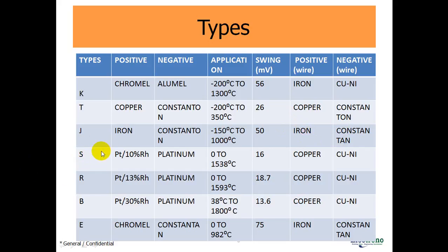Type S: it is made by platinum and 10% rhodium — meaning 90% of the material used is platinum and 10% is rhodium. The negative lead is made by platinum. Application is 0°C to 1538°C, voltage swing is 16 millivolts, and the positive wire is made by copper.